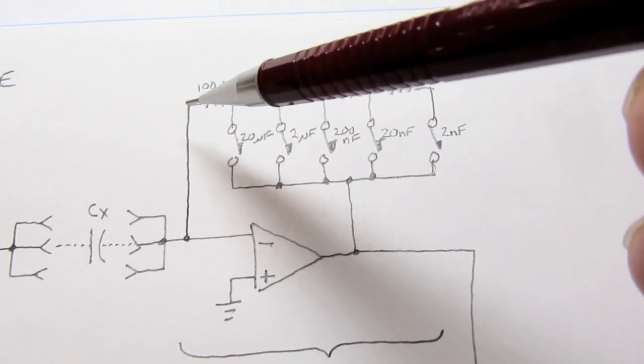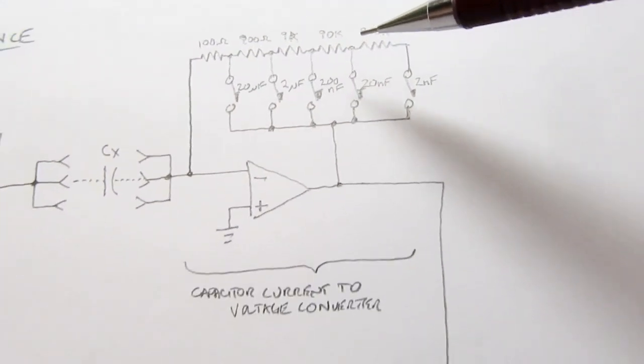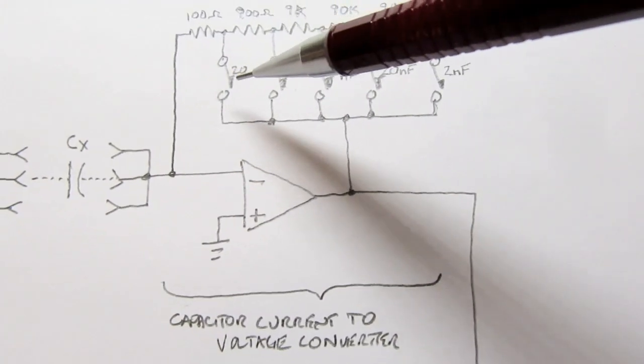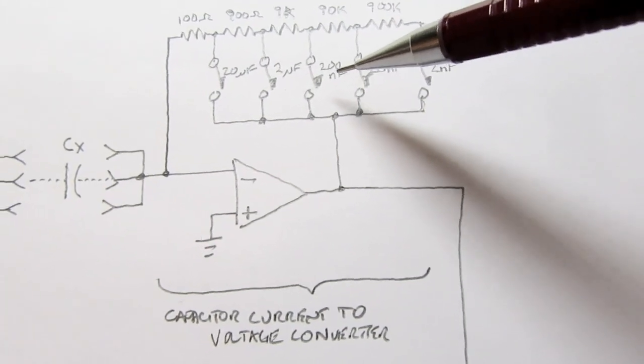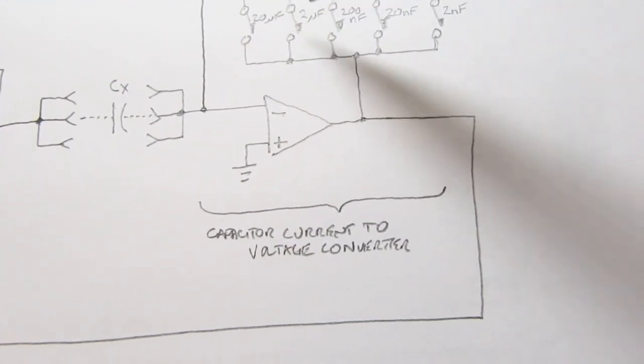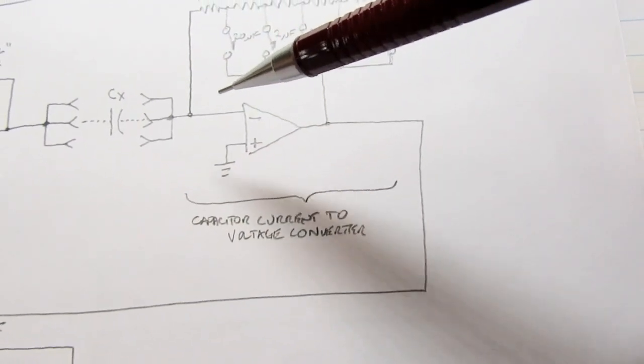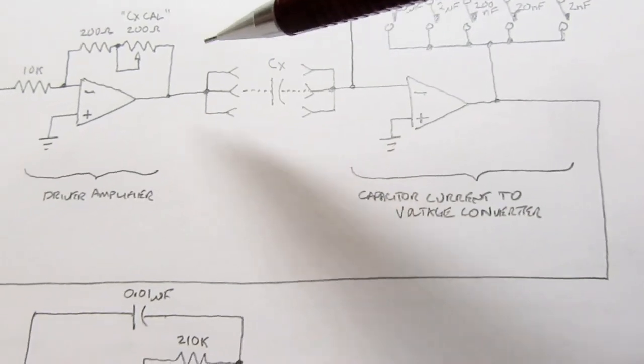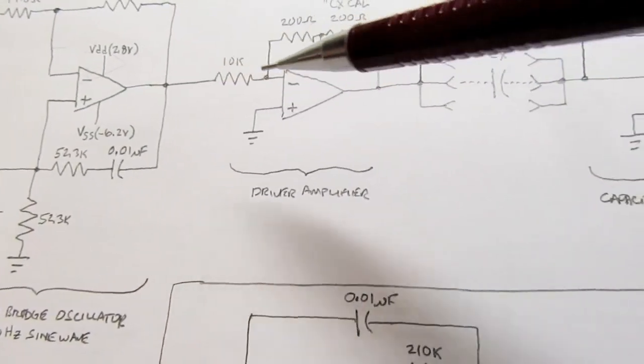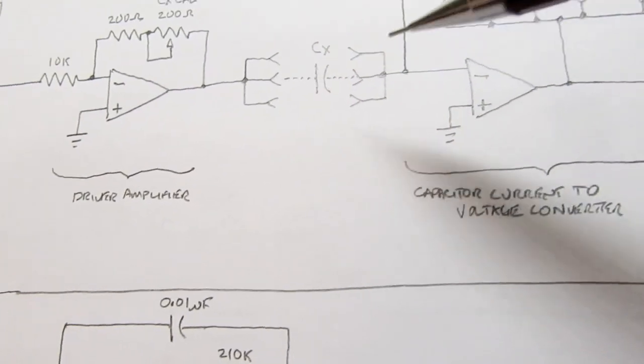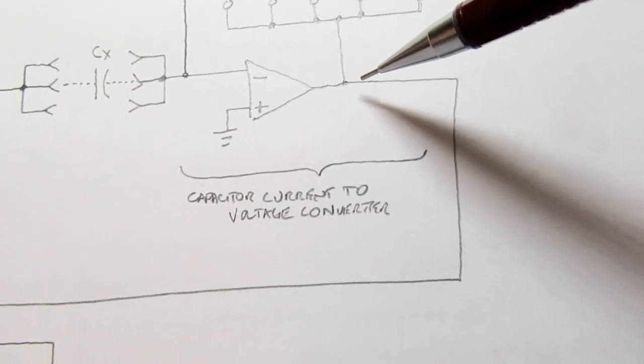900K, 90K, 9K, 900 ohms, 100 ohms, adding up to 1 megaohm for the whole thing. And you've got taps coming off on the range switches for 2 nanofarads, 20 nanofarads, 200 nanofarads, 2 microfarads, and 20 microfarads. So some combination of those resistors are connected as the feedback resistor, thereby changing the gain of this circuit, and it's acting on the 300 hertz sine wave and the capacitance of this, and that all determines what amplitude of AC signal comes out of here.